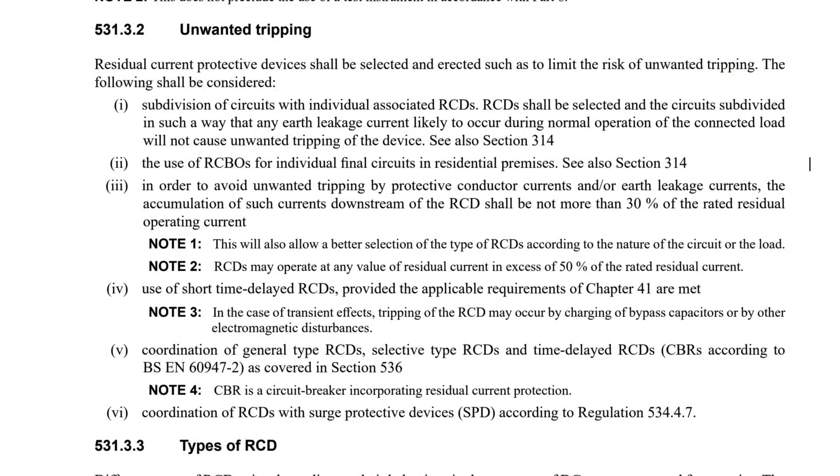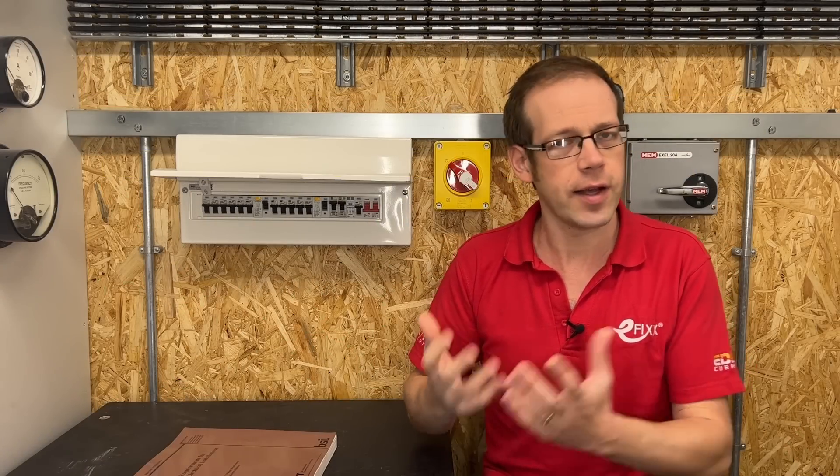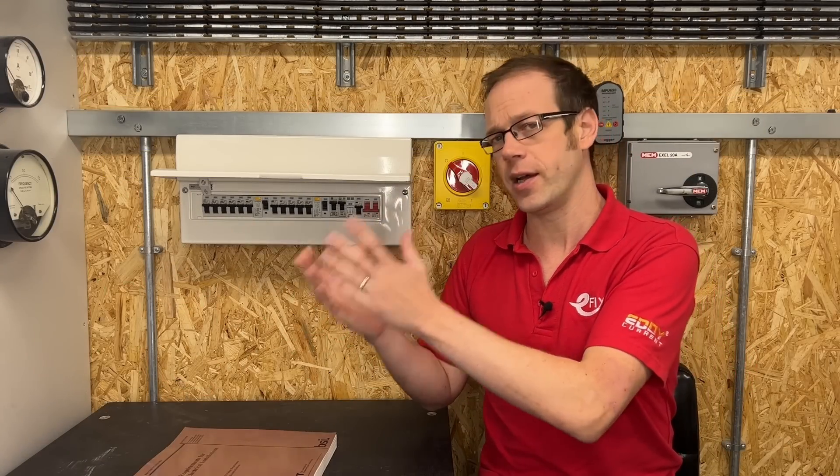So let's have a look at it now and see if split load boards are now non-compliant. It reads: residual current protective devices shall be selected and erected such as to limit the risk of unwanted tripping. The following shall be considered — and we'll jump straight to indent two: the use of RCBOs for individual final circuits in residential premises. So that seems pretty solidly in favour of RCBOs over split load RCD protection.